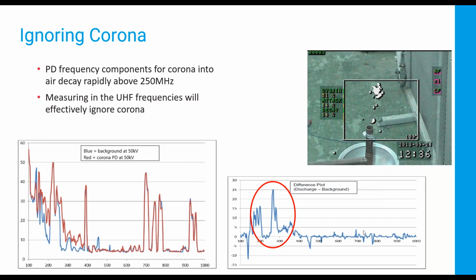So with our instrument you can scan a wide range and focus on another area of the band. We find internationally that 800 megahertz is a good starting point. Here in the US, for example, the FCC has designated that for first responders. So in your neighborhood it might be 805 or whatever, but around 800 should be a quiet range. So the instrument will allow you to scan all the frequencies, so you'd point it at the ground or away from the switch yard, scan the whole frequency range, then focus on an area that's quiet and go out and do your study.